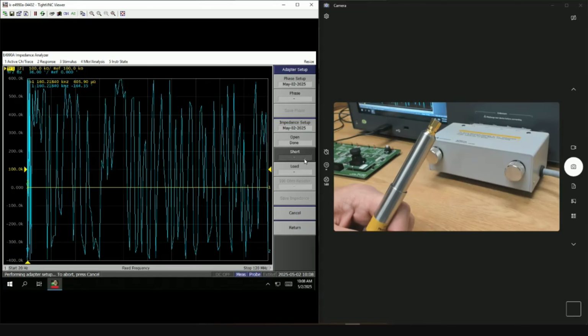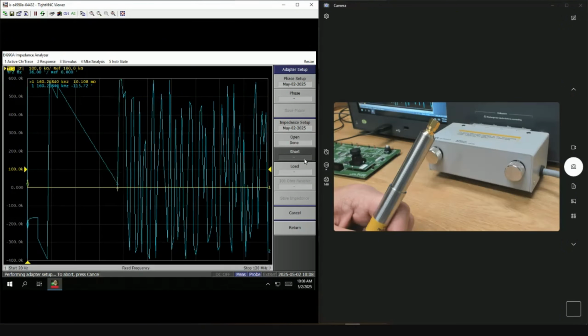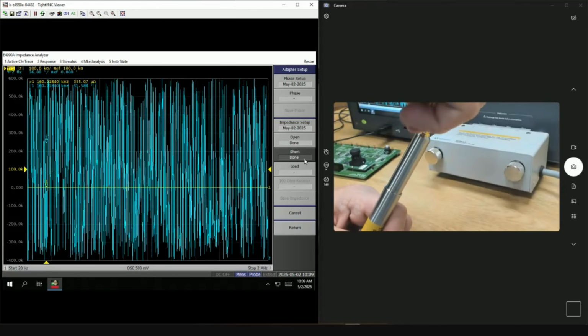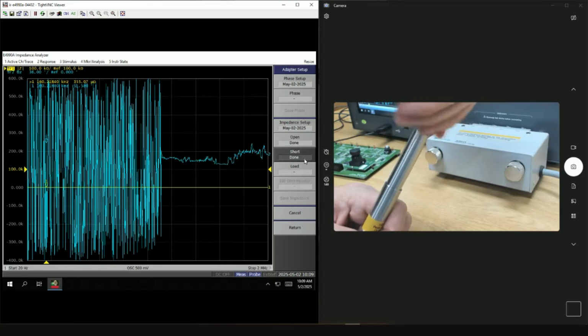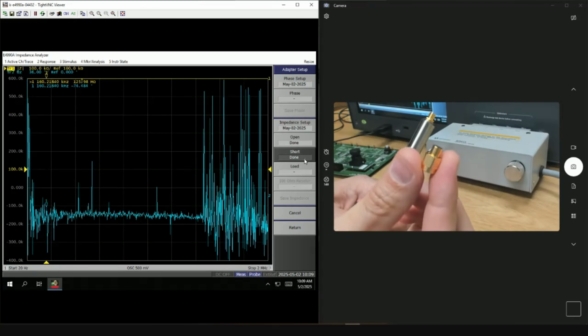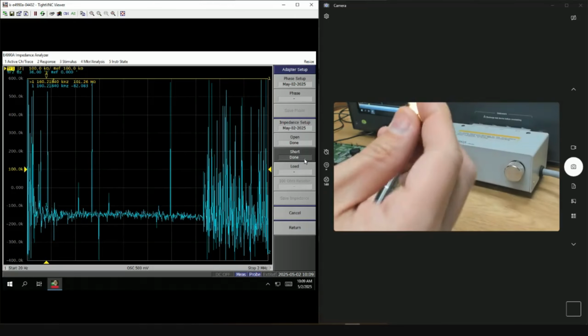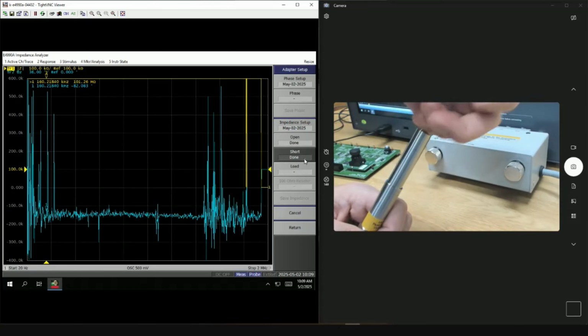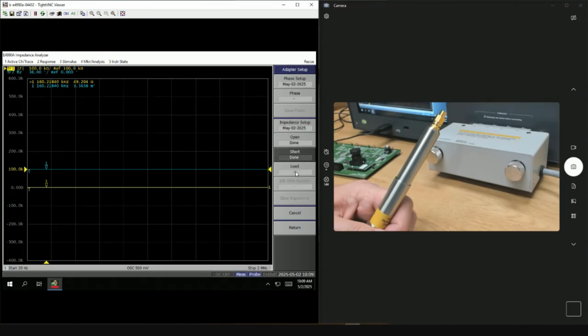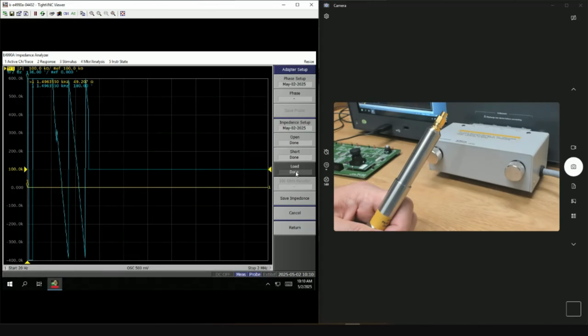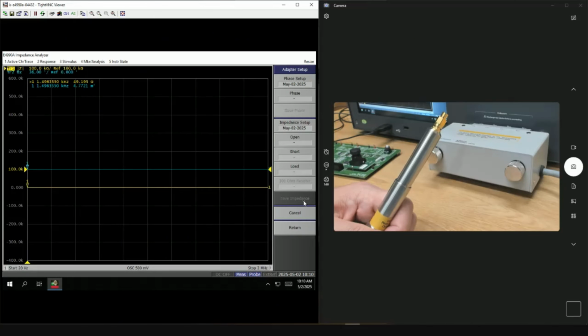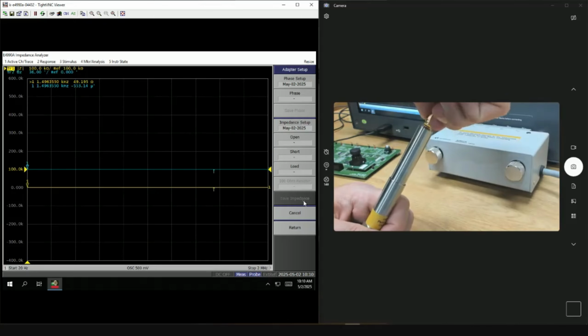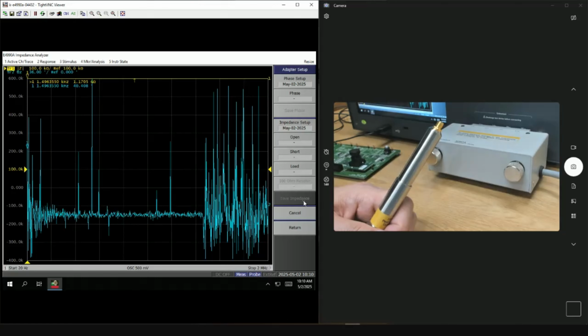Then we click short. We should be using a torque wrench for these connections, but unfortunately I do not have the torque wrench with me right now. You get the idea. Right, once it's done, undo it, keep it safely. This is the load, something protruding out, and then again connect it. Best is to use a torque wrench. Okay, then we click on load. Once done, you're going to save impedance. So your probe is ready for measurements. You are actually halfway there.